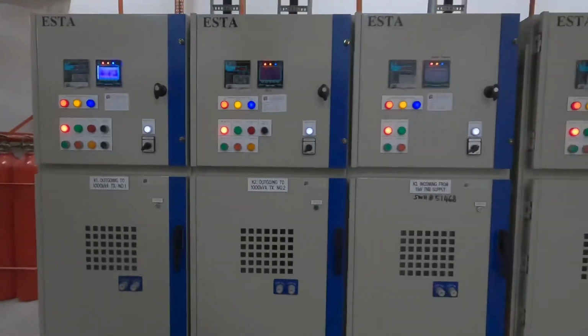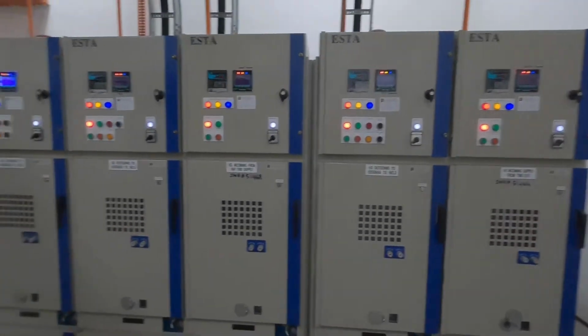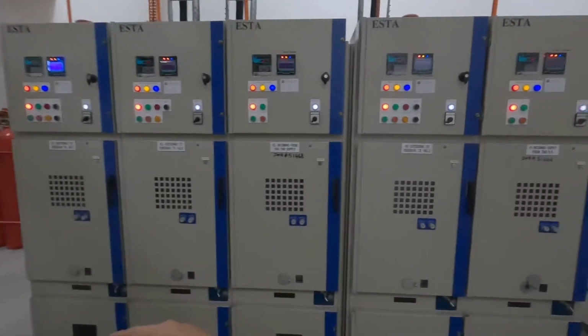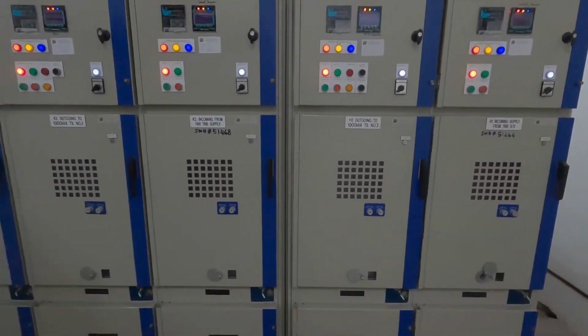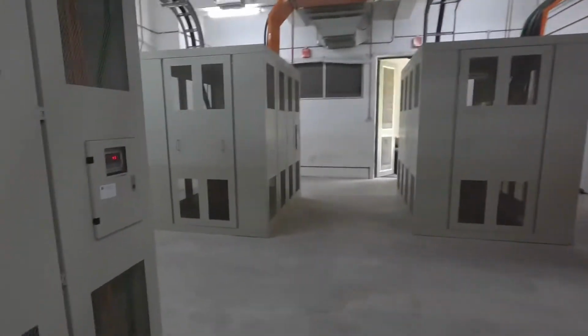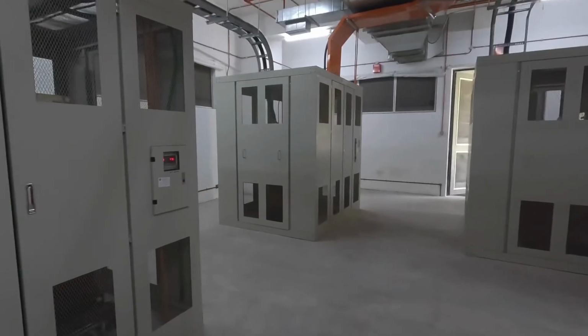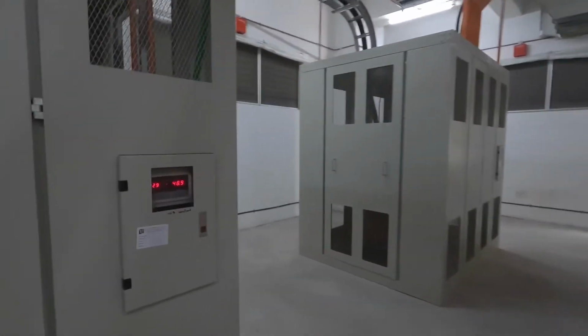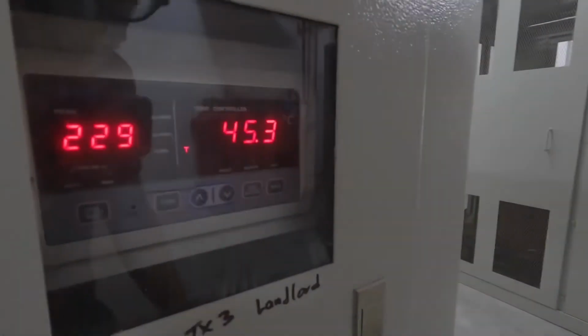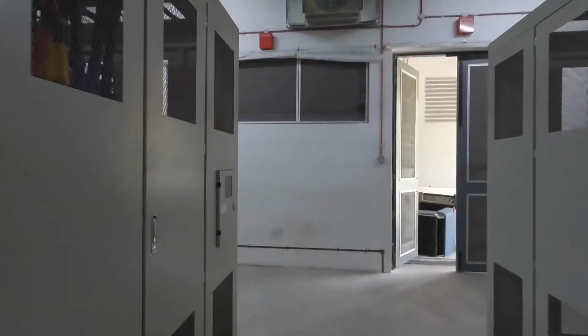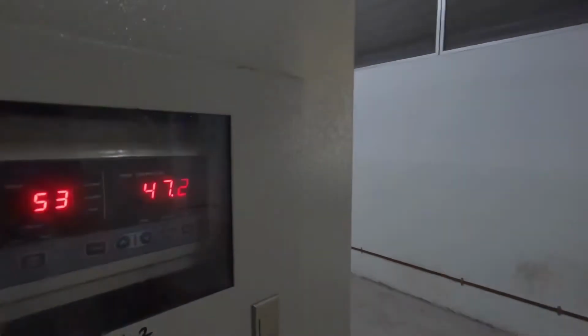The load is currently quite low. Here we have the incomer, and this is the common power supply. Total is 3 transformers, all cast resin type. Temperature is quite low, below 50 degrees Celsius due to low load conditions. As the load increases, the temperature will go up.